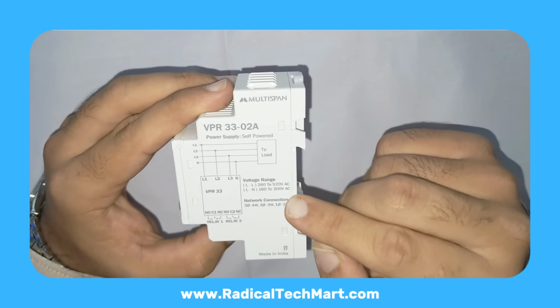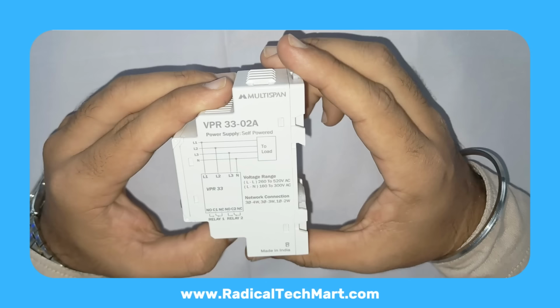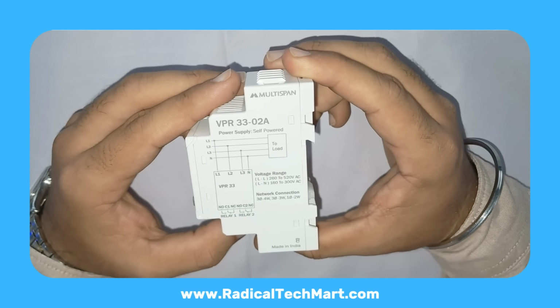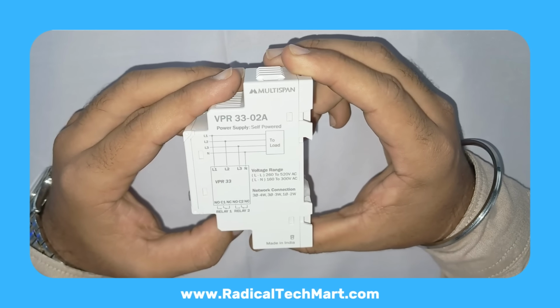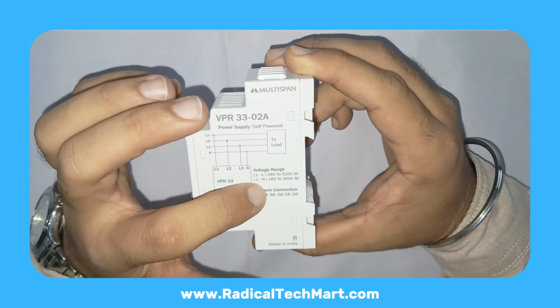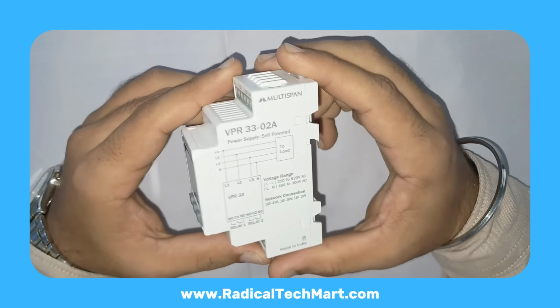In terms of network, you can use it in single-phase, 2-wire, 3-phase, 3-wire, 3-phase, 4-wire systems. Voltage measuring range. Line to line, 260 volts to 520 volts AC. Line to neutral, 160 volts to 300 volts AC.